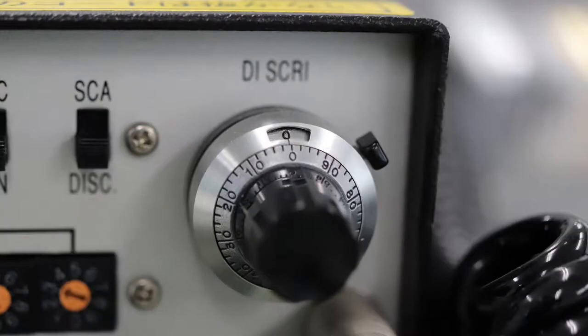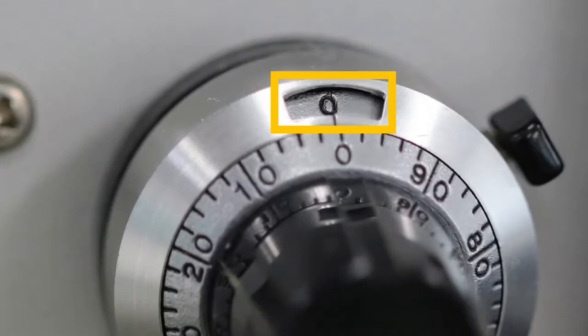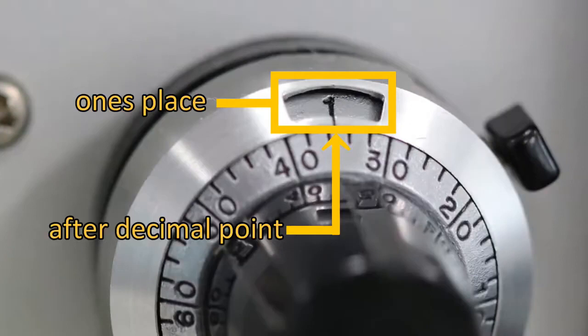The threshold value is set by this dial, which is labeled DISCRI. Such a dial is called a helipot. Let me explain how to use it. When the dial is turned once, the number in the square window goes up by one. The number in the square window is 1's place, and the scale of the dial represents the value after decimal point. Since the number in the square window is 1 and the dial is 35, the value at this time is 1.35.